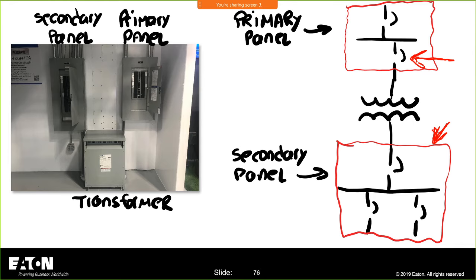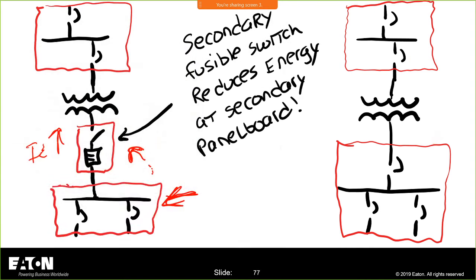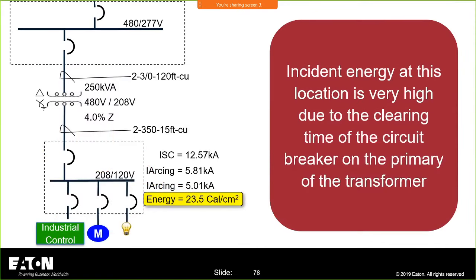If I don't understand, if my drawings aren't correct and they're not updated correctly, I could make the false assumption. But having an overcurrent device there, in any case, can extremely reduce the incident energy. So I'm going to run through this quick example of a 250 kVA transformer with 4% impedance. I think this whole concept I'm going to share with you is one of the best I've seen, and it's such a simple concept. In this case, I have a 250 kVA transformer with a 4% impedance. My incident energy at that first panel board is 23.5 calories per centimeter squared.